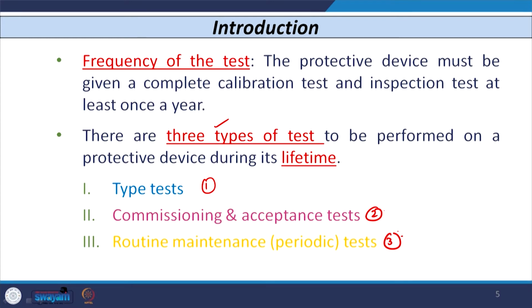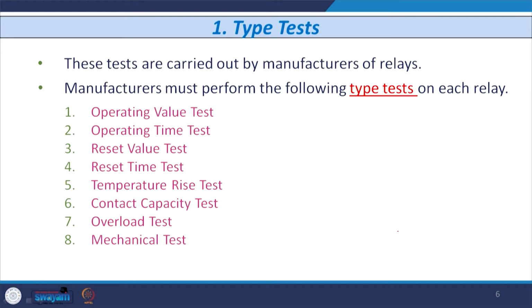So, let us start with how the type testing of the protective device is to be carried out. This type of test is usually carried out by manufacturers. The manufacturers who are manufacturing the relays need to perform the type test on the relay or protective device. The manufacturer has to perform the following type tests on each and every relay. The first is the operating value test, the second is the operating time test, the third is the reset value test, the fourth is the reset time test, the fifth is the temperature rise test, the sixth is the contact capacity test, the seventh is the overload test, and the last is the mechanical test.